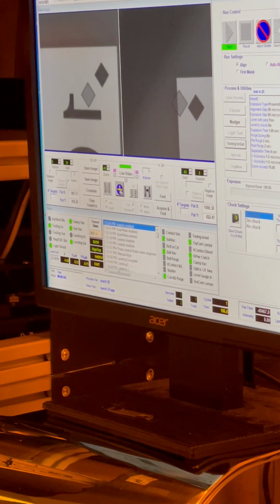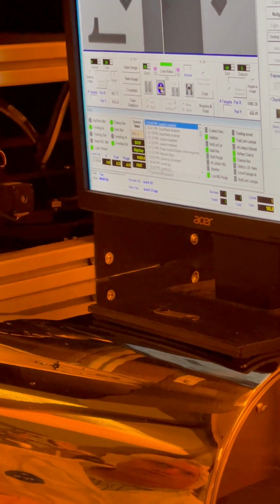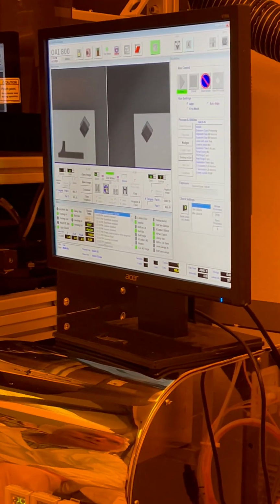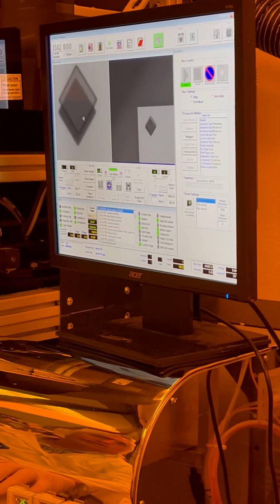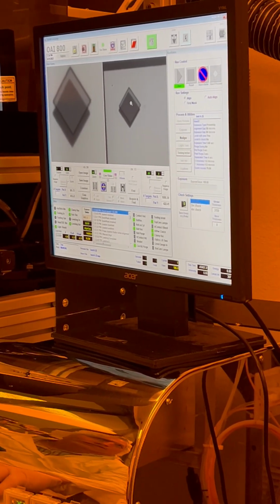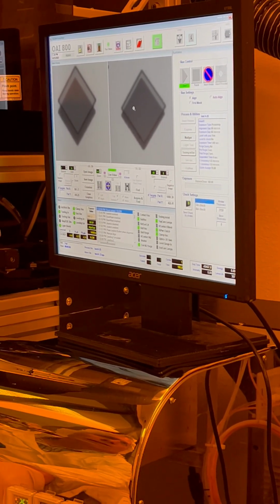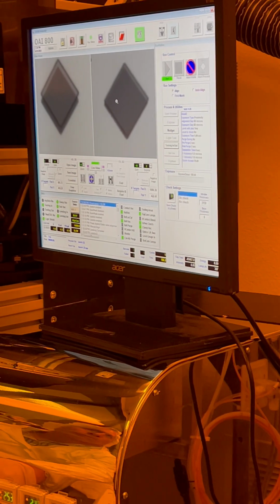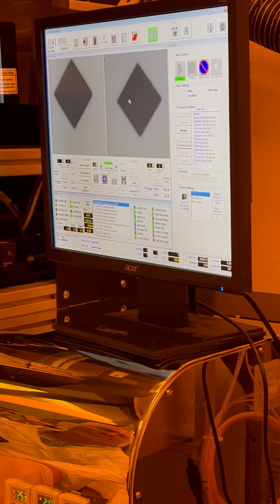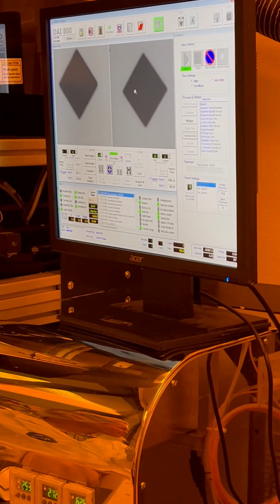The joystick does have functionality. If I'm doing a manual alignment, and I hit the space bar, now the chuck speed is slow, and I'm doing very, very fine alignment. If I want to see what's going on, I can get in there and get this really lined up. I hate doing alignment, but the auto alignment is so good, so nice to have. It's like, wow.